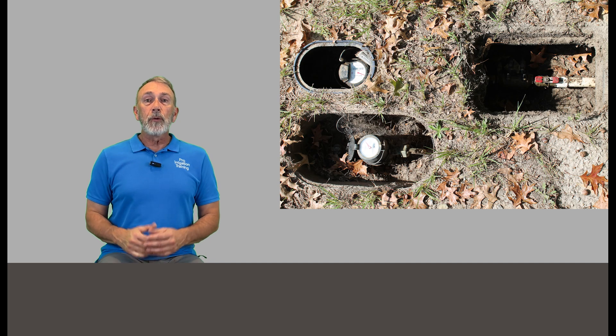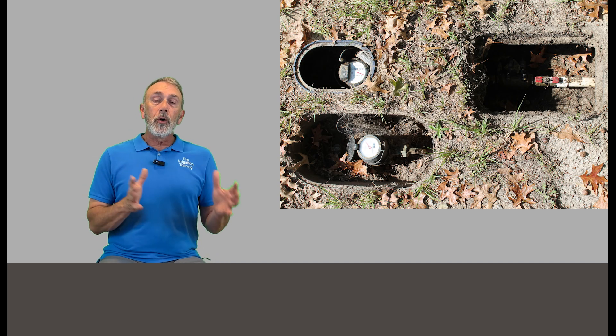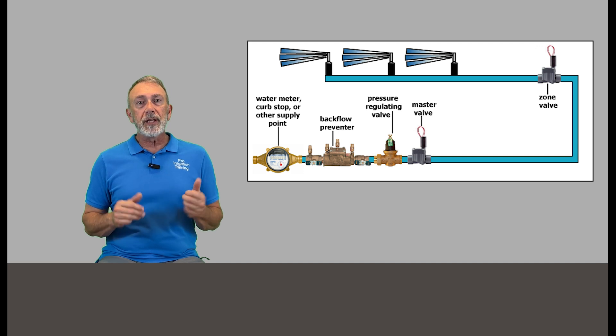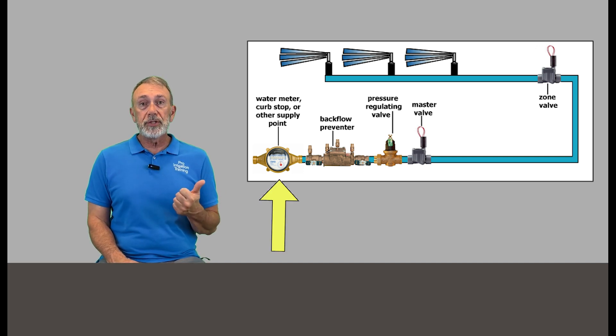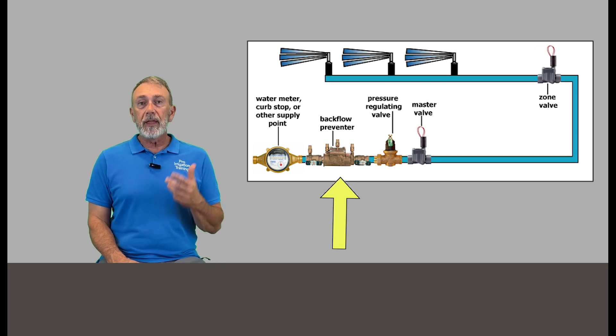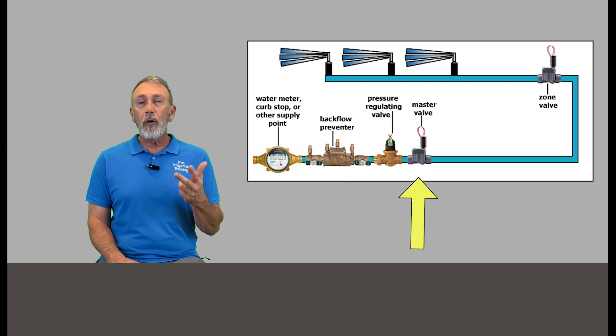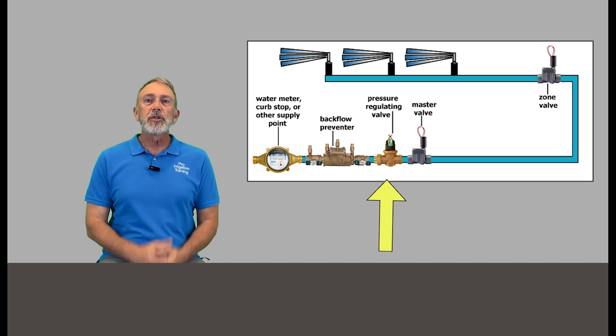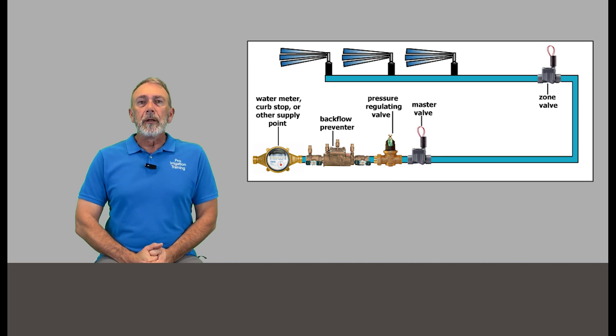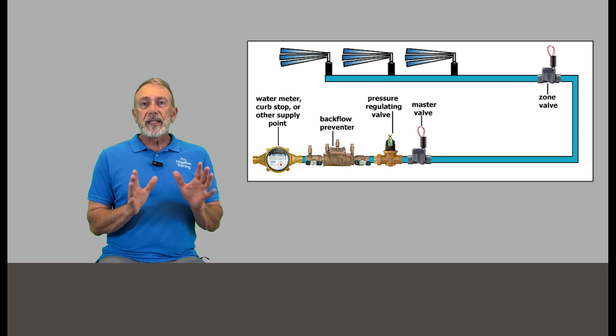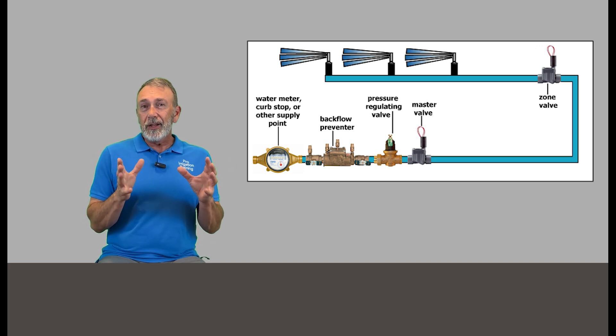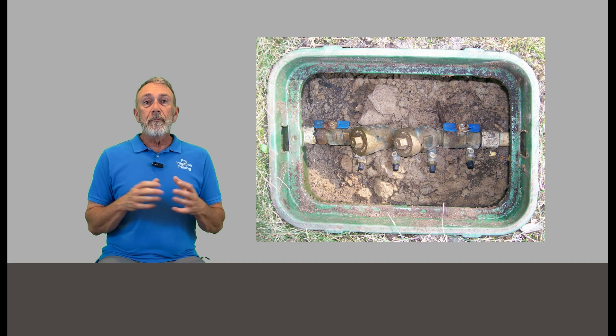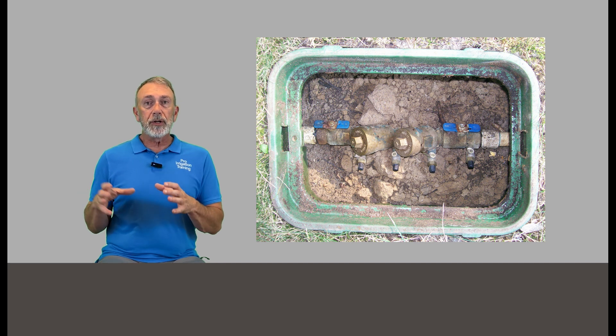As we walk around, we're going to identify where the meter and backflow preventer and all that stuff is. We're going to check our control valves that's on our main line and that should consist of a meter or curb stop. Next up should be the backflow preventer and then if you have a master valve, it should be after that or the pressure reducing valve. Sometimes they get swapped in order there. We're really looking for any of these type of valves that's present. If you have a backflow preventer that's mounted underground in a valve pit, it may be that you have the master valve or pressure reducing valve in a smaller, maybe a round valve box, a round valve tube.